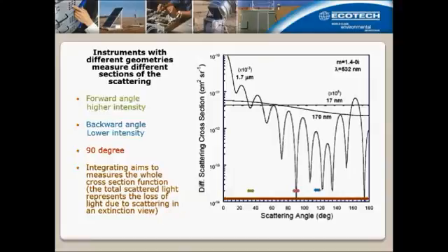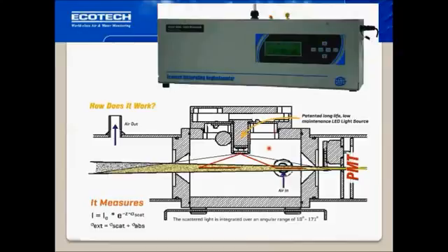When you look into measuring the whole scattering angle, there is one way you can do that. And here it's basically shown what you do when you want to measure the whole angle area. You have a light source here illuminating a particle loaded area, and the cone is the light cone. The light exiting the light source at an angle like that hits a particle here, and the light gets scattered towards the detector, so you have a scattering angle which is basically a backward scattering from here to here. Light going in the forward direction hits a particle here, gets scattered in that area, measured here, and you have a smaller angle, a forward angle scattering, and all gets measured with the photomultiplier.